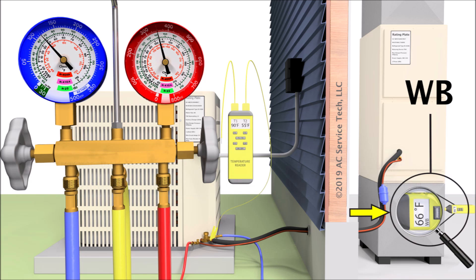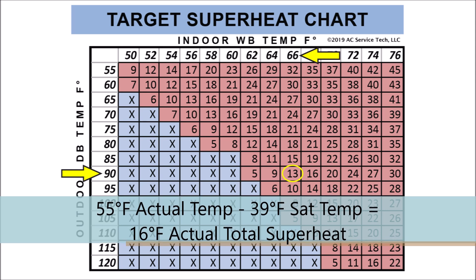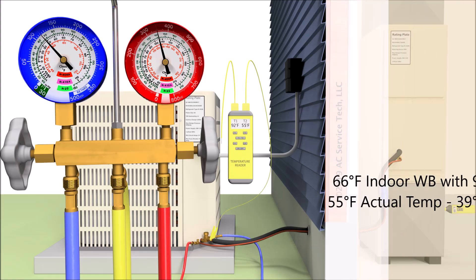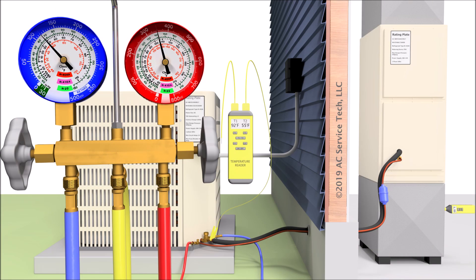We now see that the indoor wet bulb temperature is reading 66 degrees, and the outdoor dry bulb temperature is now 92 degrees — two degrees of change on each. You constantly have to monitor those temperatures because your target superheat is a moving number. It's not a constant number like the subcooling rating on the outdoor unit. So if our target superheat is now 13 degrees and our actual superheat is 16 degrees, then we're just slightly undercharged and could add a little bit of refrigerant — maybe literally a half an ounce or a very small amount. We are three degrees off from our target superheat.